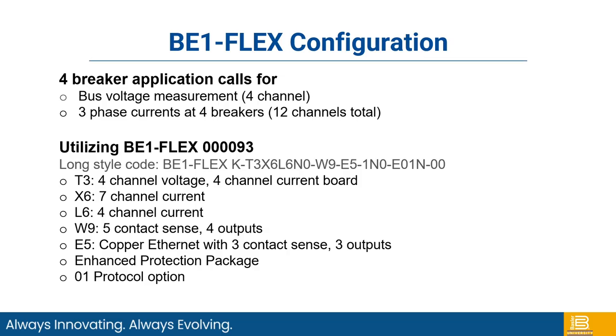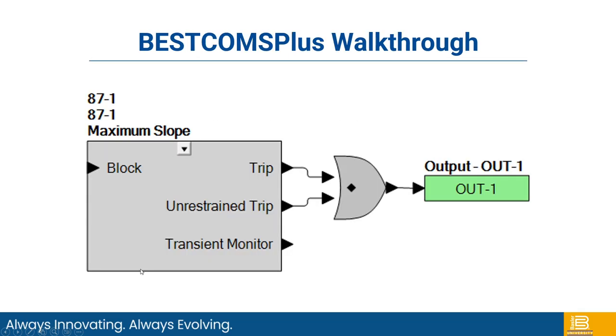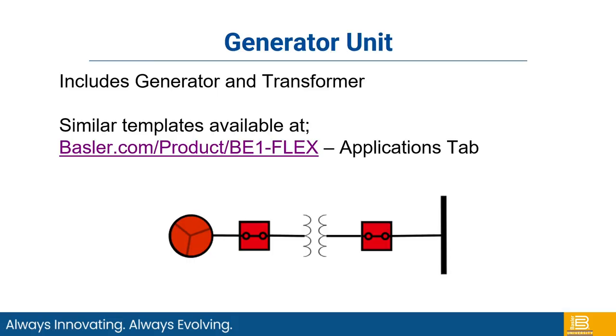I selected in mine 2X6 because the cost difference is not much. So you might want to optimize and have some extra spares. Same with the extra output contacts, because I had the available slots. You can put that in, but you don't need to. The enhanced protection, the copper Ethernet, and Modbus and DNP. Then you go through, create your setup, and you build your logic here with the 87 for the unrestrained and the restrained trip going to output 1. And you also put in your protection, etc.